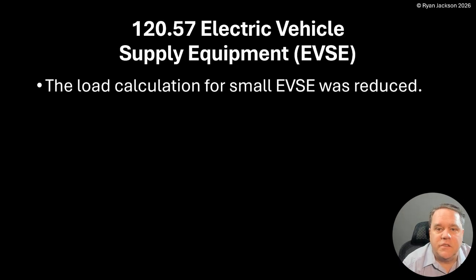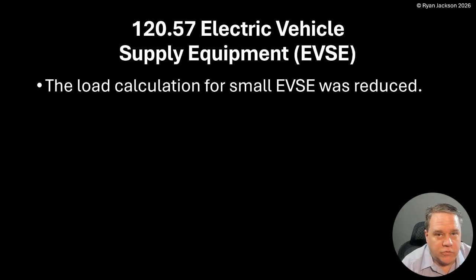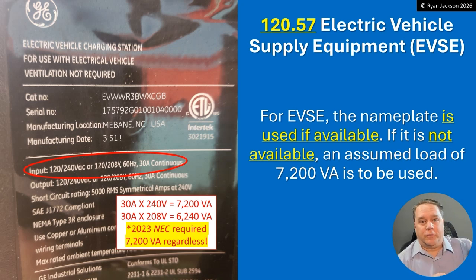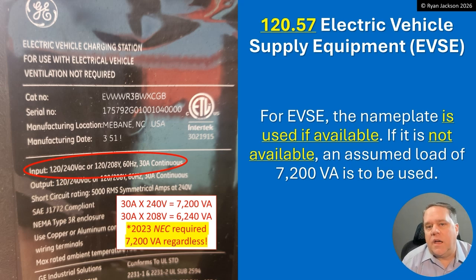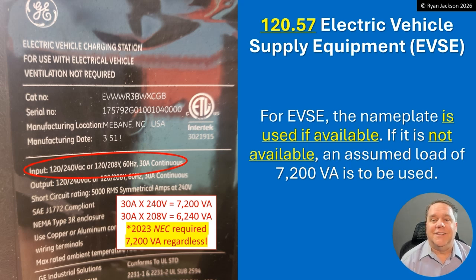120.57 covers electric vehicle supply equipment. The load calculation for small EVSE was reduced. This was added in the 2023 code — fortunately — because before there was nothing. If there's no guidance on load calculations, here's an interesting way to look at it: all Article 120 does is allow you to use less than the nameplate. That's the whole concept of Article 120.